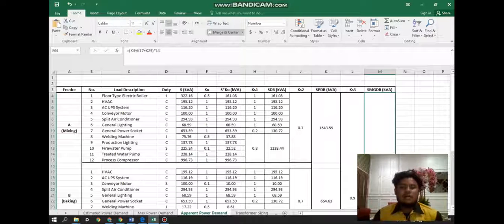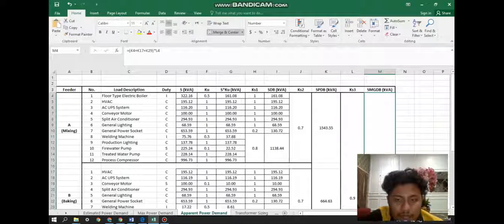Okay, so KS1, 2 and 3 may now be used to identify the rated diversity factor, the KS, for each load separately. So the KS1 rated diversity factor is 1.0 based on the utilization factor for each heavy machinery given in this Excel. The rated diversity factor of 0.2 was used for the less heavy loads. For KS2, the rated diversity factor is determined by comparing the rated diversity factor stated in KS1 to the total specified loads, where 0.7 is the appropriate rated diversity factor.